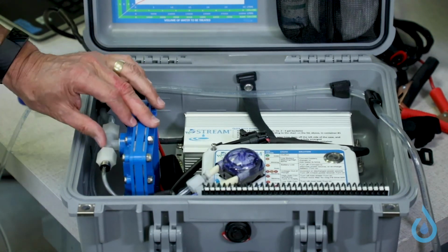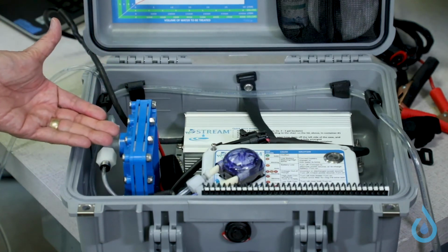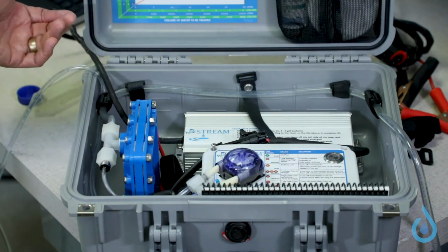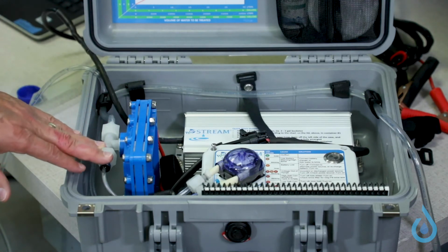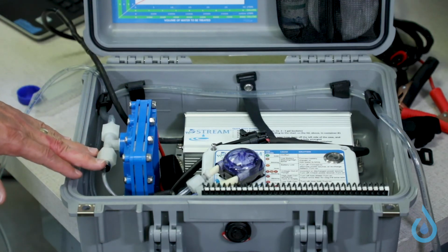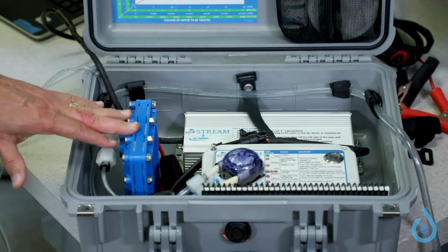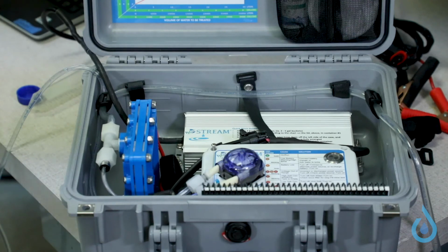Now when it restricts the flow like that, the flow rate is slower, there's not as much heat being removed in the liquid, and it'll get warm coming out. So the temperature is monitored again with the thermal well, and if it gets too warm, then the system will shut down and you will see the red, green, red flashing light.